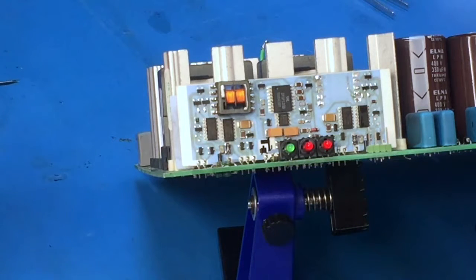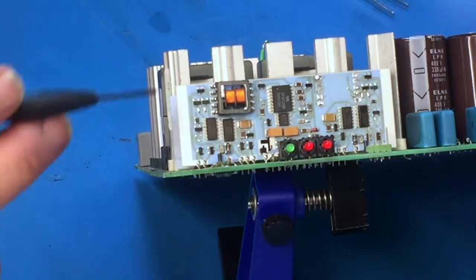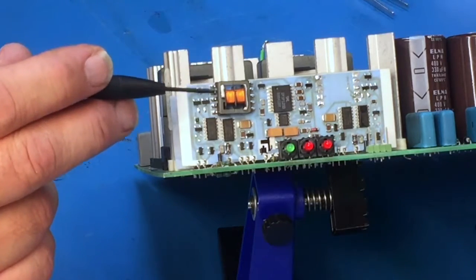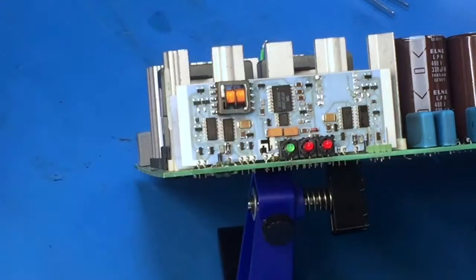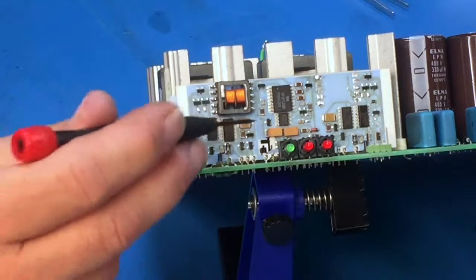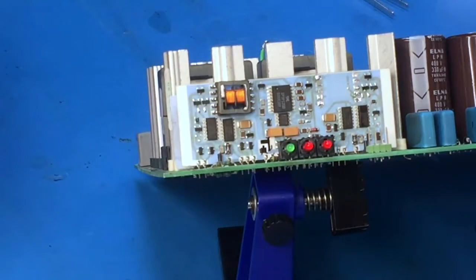When we powered this power supply up, there was no output. Diagnostic tests showed the reason was the failure of this pulse transformer, which is part of the gate drive circuit for the chopper for the primary side switching of the power supply. So we need to remove this transformer and replace it with a new, good one.